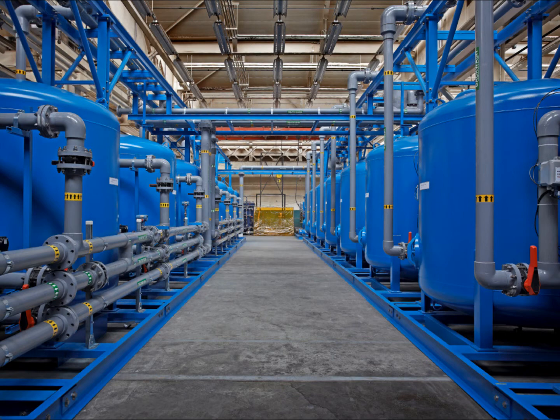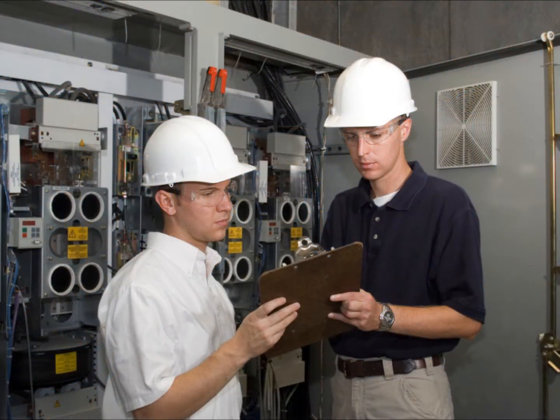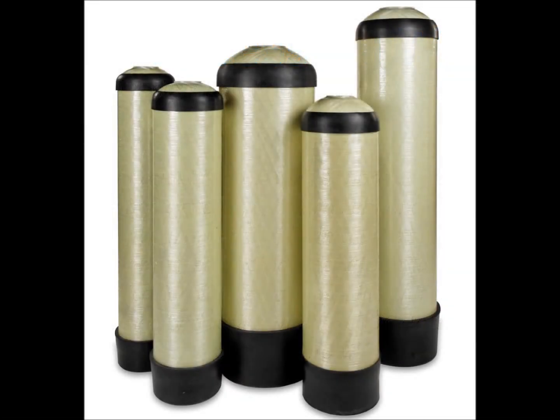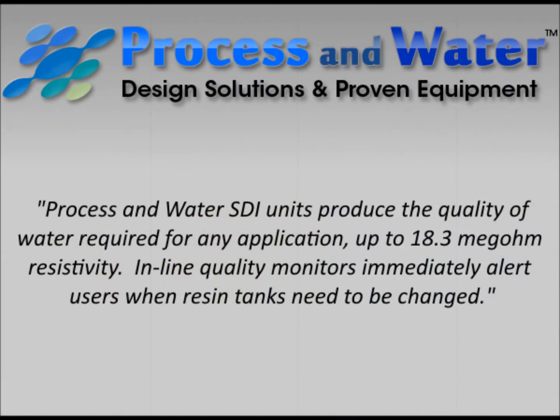A variety of anion resins are available suitable for any water application. For higher quality water with a more neutral pH than separate bed systems, as well as enhanced silica and CO2 removal, mixed bed resin can be a stand-alone system or placed as a polisher after the separate two beds — cation and anion resins. Process and Water utilizes premium grade mixed bed resins with low TOC (total organic carbon) throw. Process and Water SDI units produce the quality of water required for any application, up to 18.3 megohm resistivity.